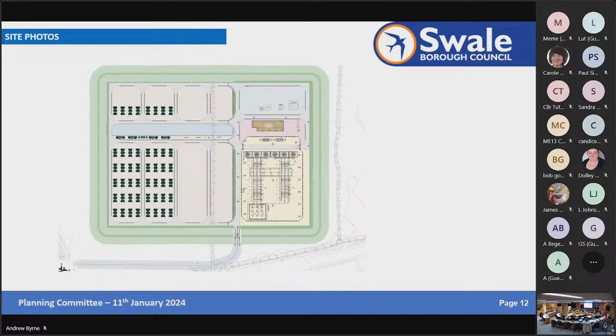With regard to water systems, all the cases stated with extrapolated volumes of water occurred from incidents where the BESS enclosures did not incorporate internal water sprinkler or spray systems. Sometimes there wasn't an emergency response plan for the fire service, so no strategy had been agreed, meaning they were going into the field a little blind in some of those cases.